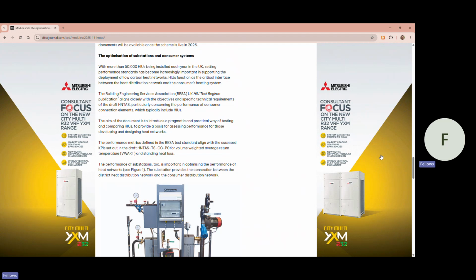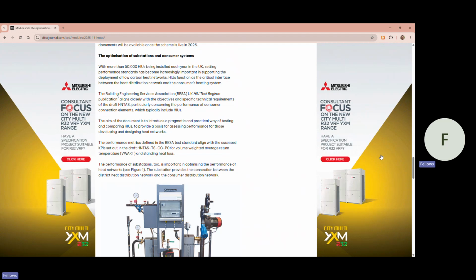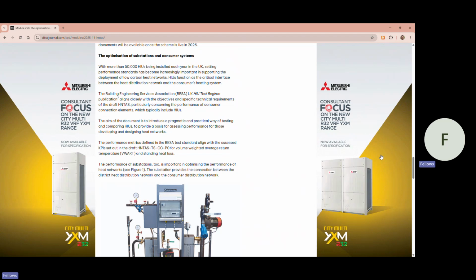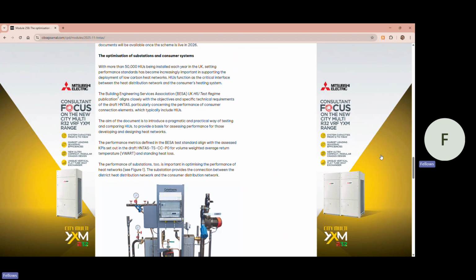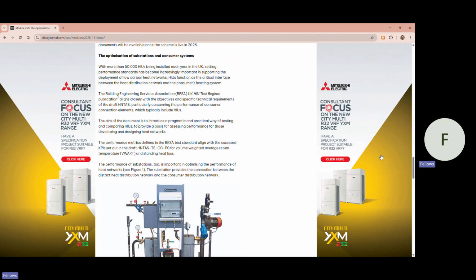The performance metrics defined in the BESA test standard align with the assessed KPIs set out in the draft HNTAS TSCC P0 for volume-weighted average return temperatures, VWART, and standing heat losses. The performance of substations, too, is important in optimizing the performance of heat networks.